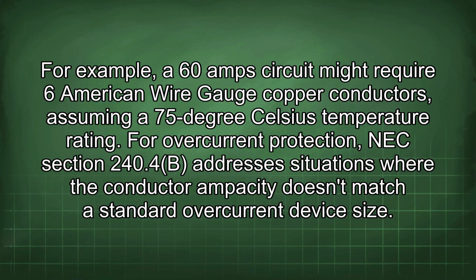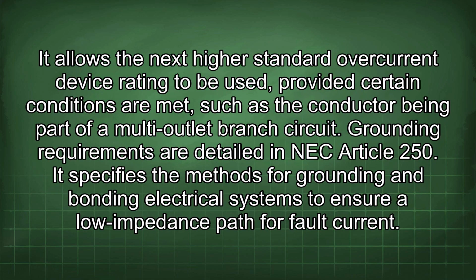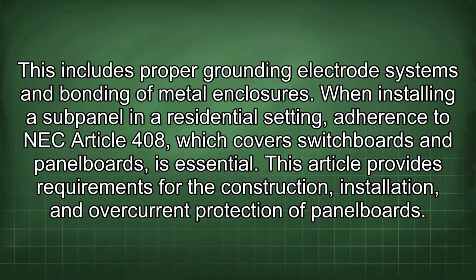For overcurrent protection, NEC Section 240.4(B) addresses situations where the conductor ampacity doesn't match a standard overcurrent device size. It allows the next higher standard overcurrent device rating to be used, provided certain conditions are met, such as the conductor being part of a multi-outlet branch circuit. Grounding requirements are detailed in NEC Article 250. It specifies the methods for grounding and bonding electrical systems to ensure a low impedance path for fault current. This includes proper grounding electrode systems and bonding of metal enclosures.